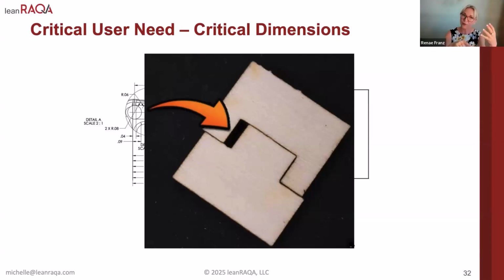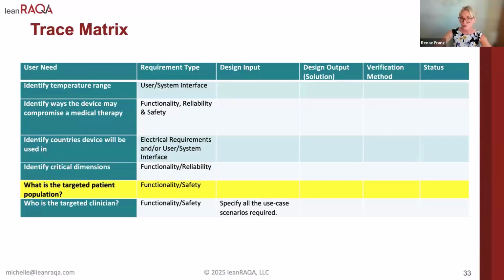What was happening is they were applying the radio frequency energy to the tubing. The device was sparking because the two jaws were not meeting evenly and they were burning through the tubing. So not only were 10 families affected, they were saving this cord blood for a reason, but also each unit of lost cord blood cost the Singapore Blood Bank $50,000. So identify your critical dimensions up front and make sure that you actually do your QC for those as you're bringing the products off the manufacturing line.